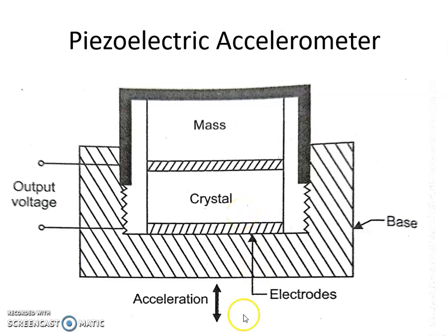So when acceleration is applied to the base, obviously force is applied to the crystal against the mass. Now when force is applied to the crystal, it develops an EMF or voltage across its surfaces, which can be measured through the electrodes and connected wires.